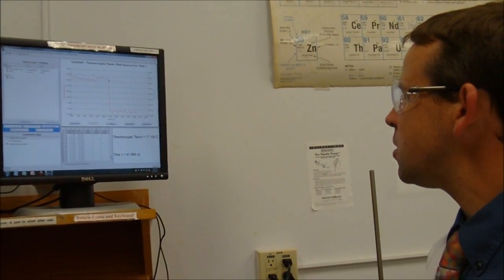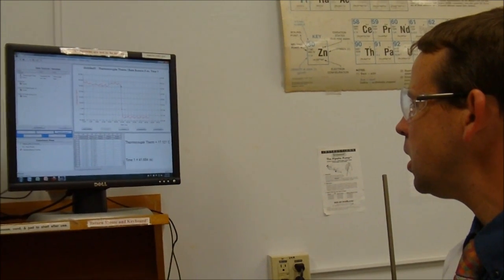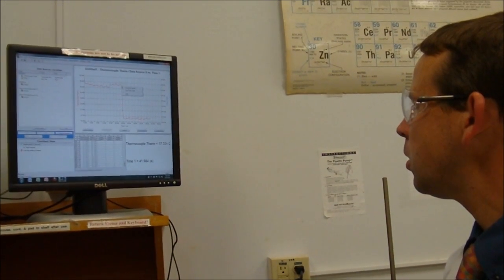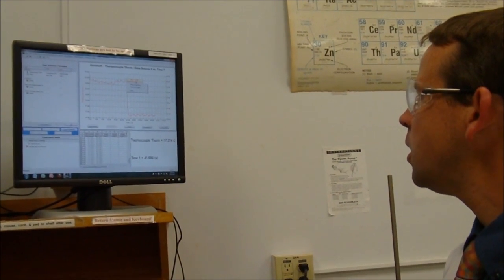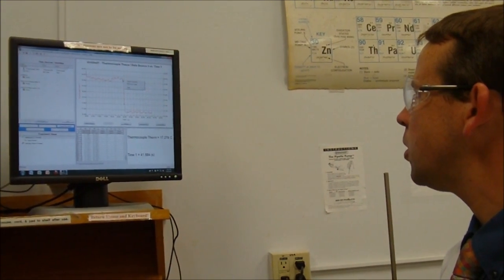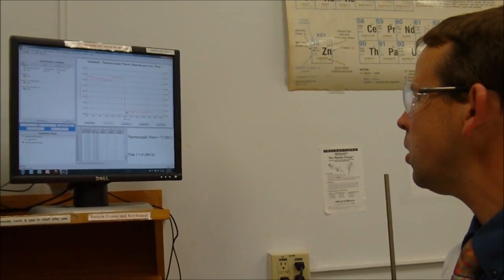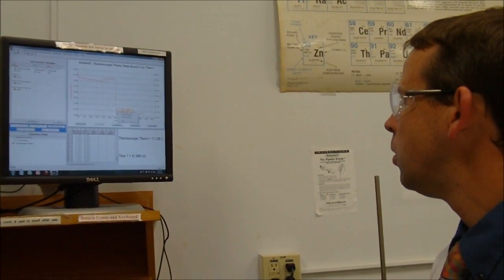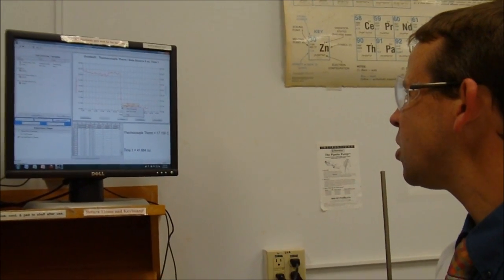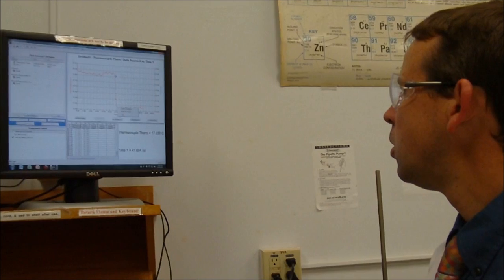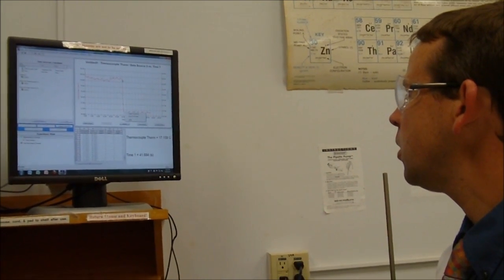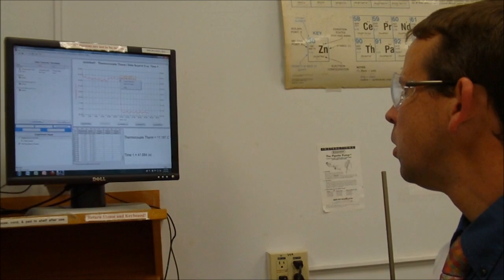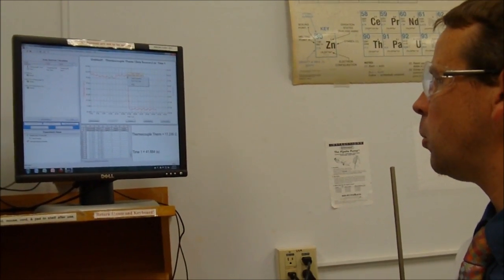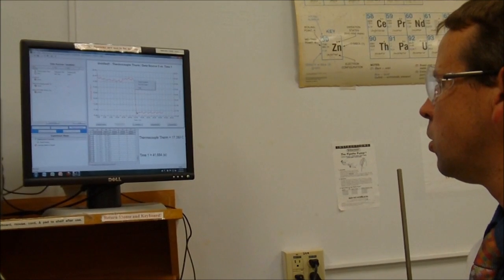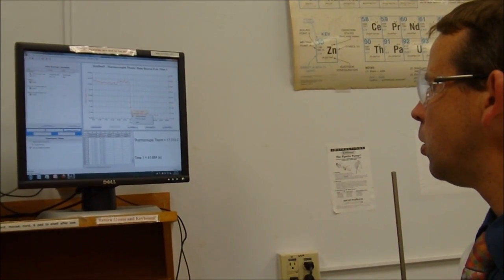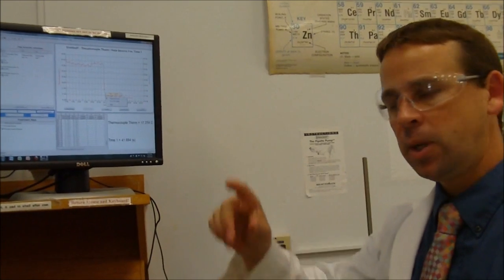I don't know exactly, let's see, if I rest right here and click right there, does it tell me that data? Right click, graph proper, oh there we go. It tells me it's 23.38. So there's my temperature right there. If I click right here, 24.90. Oh no, sorry, 17.2. 17.2 is it. And did I get the right value there when I went here? The temperature was 20.1, 20.11. So 20.11 down to 17.24. So there's my delta T. I can get that value.